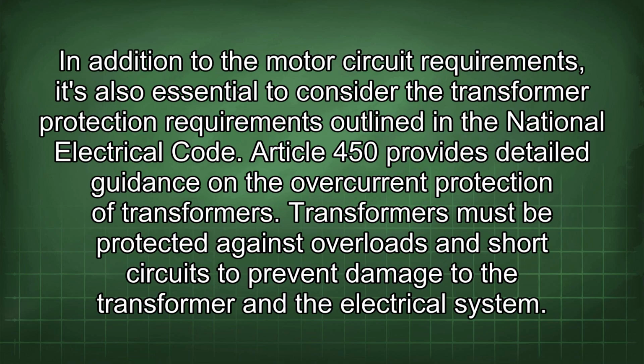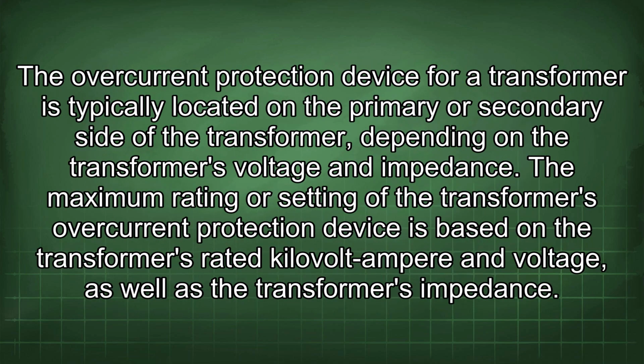In addition to the motor circuit requirements, it's also essential to consider the transformer protection requirements outlined in the National Electrical Code. Article 450 provides detailed guidance on the overcurrent protection of transformers. Transformers must be protected against overloads and short circuits to prevent damage to the transformer and the electrical system. The overcurrent protection device for a transformer is typically located on the primary or secondary side of the transformer, depending on the transformer's voltage and impedance. The maximum rating or setting of the transformer's overcurrent protection device is based on the transformer's rated kilovolt-ampere and voltage, as well as the transformer's impedance.